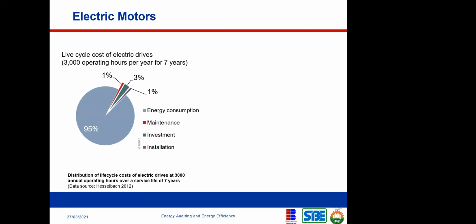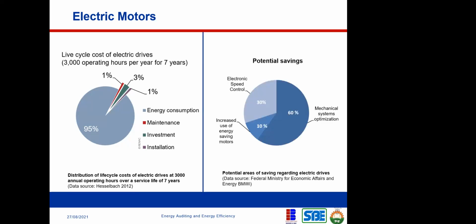So it's very, very important that when you're buying a motor, you buy a motor that has a higher efficiency rating. Because the one with lower efficiency rating might cost less, but that is insignificant. The bulk of the expenses is in running that motor, in operating that motor, right? So you can see from these statistics that 95% of the total cost of owning that motor is in the electricity consumption. So what are the potential savings?